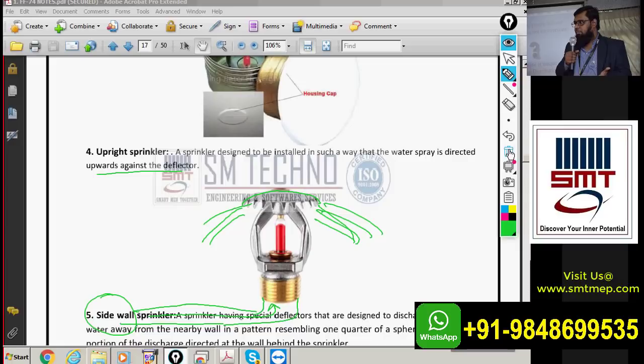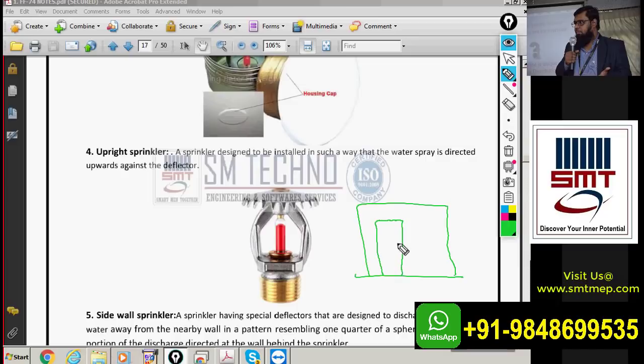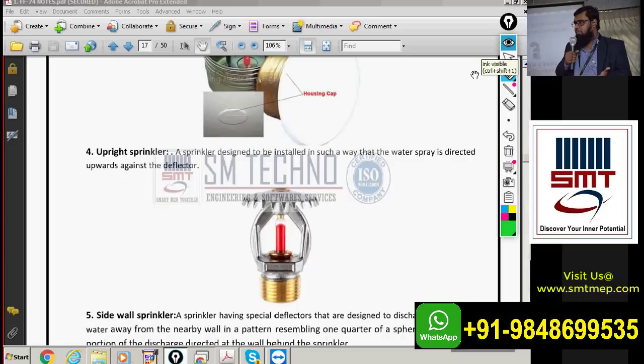A best example of upright sprinklers is a store area, where there is generally no false ceiling. If I use pendant sprinklers in a store room with tall items like almirahs, the water flow may be restricted. Upright sprinklers direct water upward first, then it covers a wide area even around obstructions. Upright sprinklers are also used to cover the space above the false ceiling where services run.